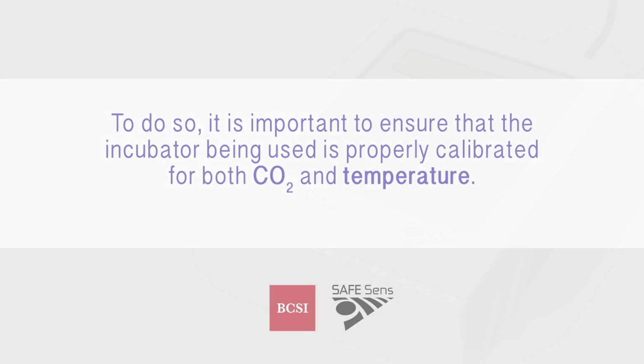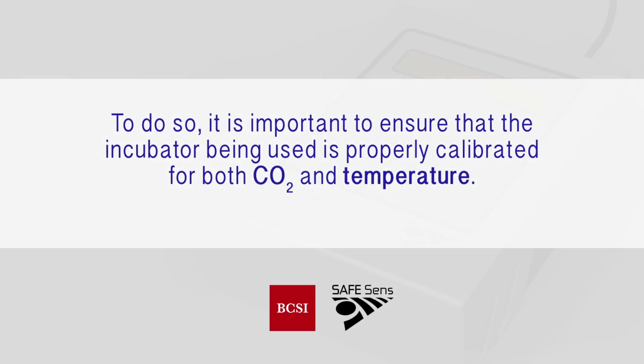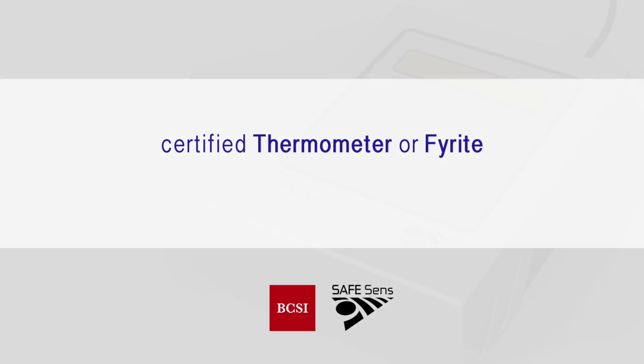in your clinic. To do so, it is important to ensure that the incubator being used is properly calibrated for both CO2 and temperature. Verify the temperature and CO2 by an external method such as a certified thermometer or Fyrite before beginning your setup tests.